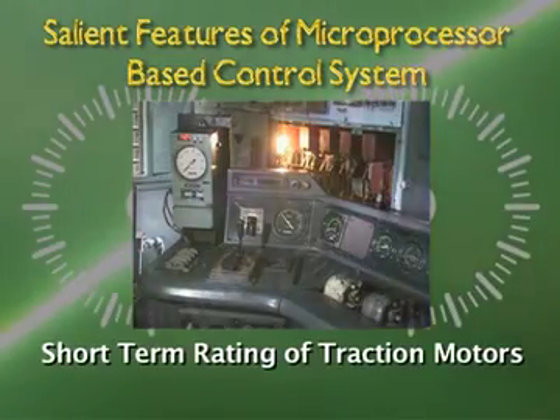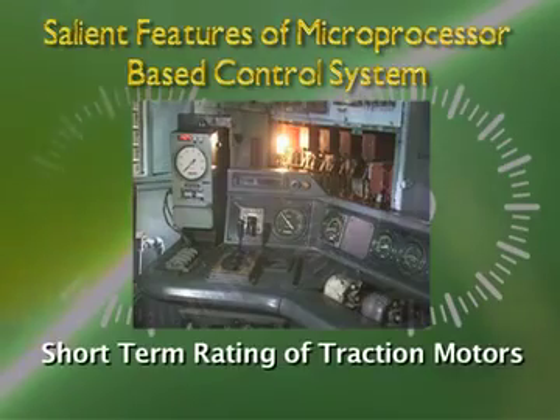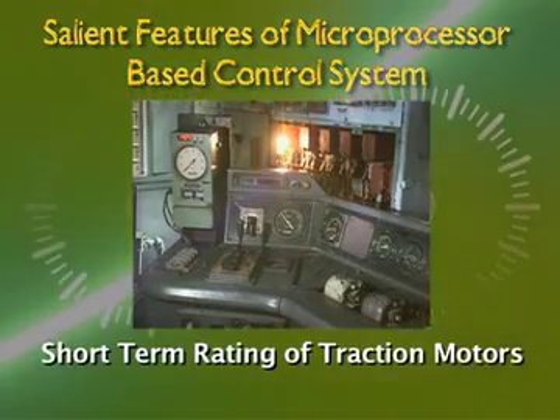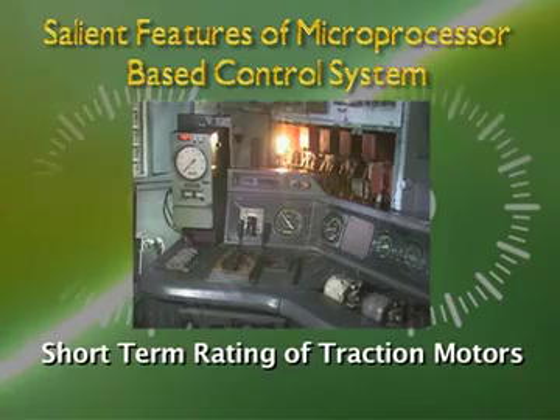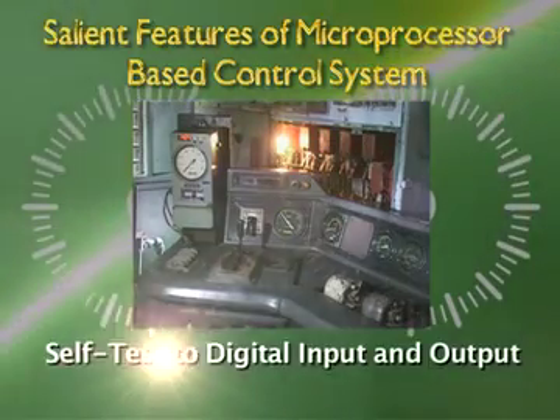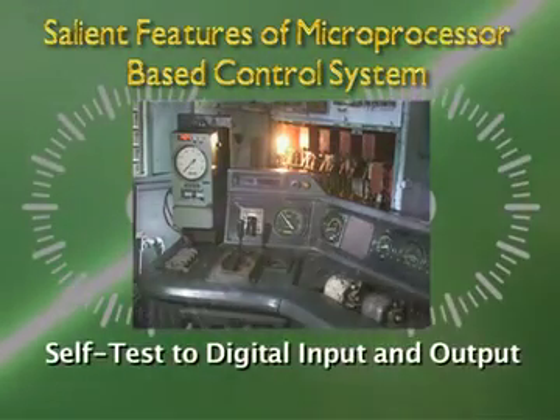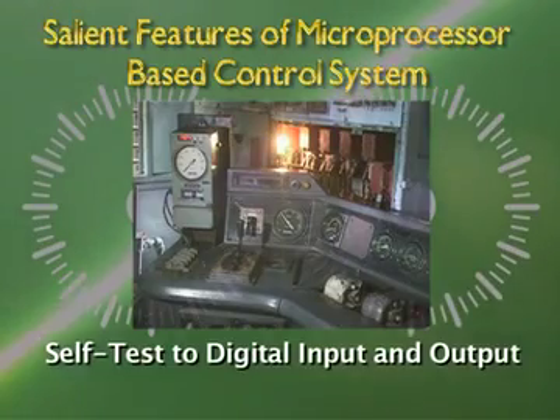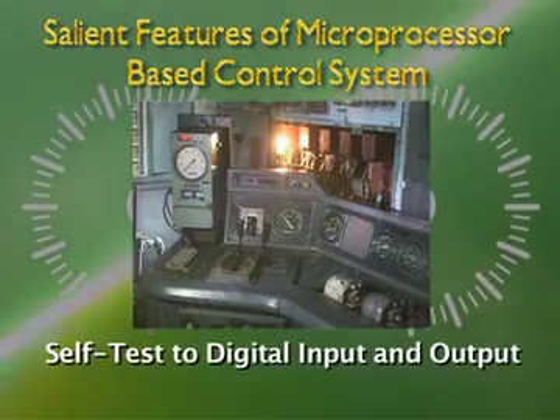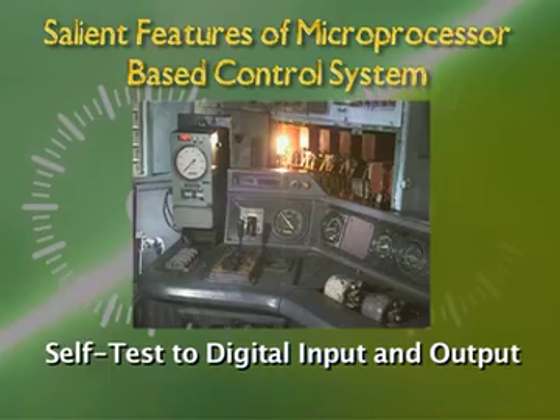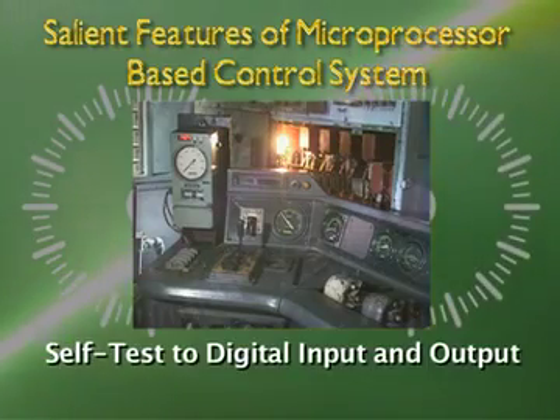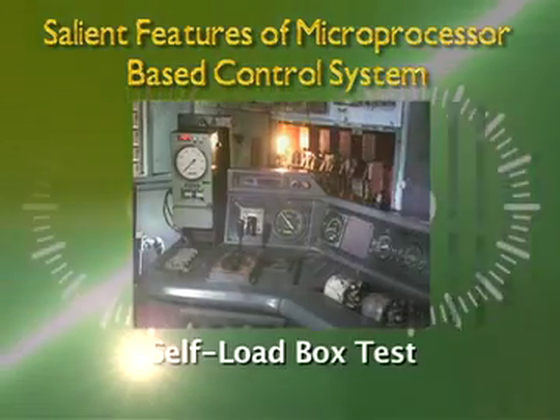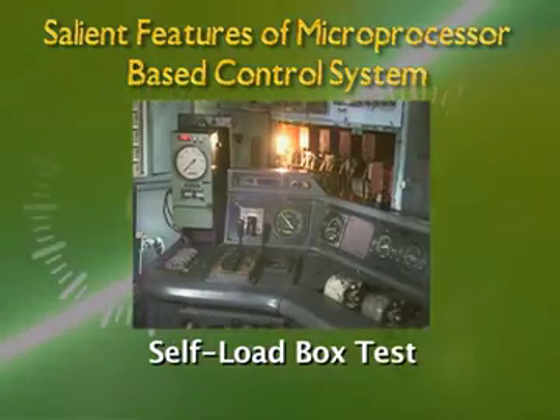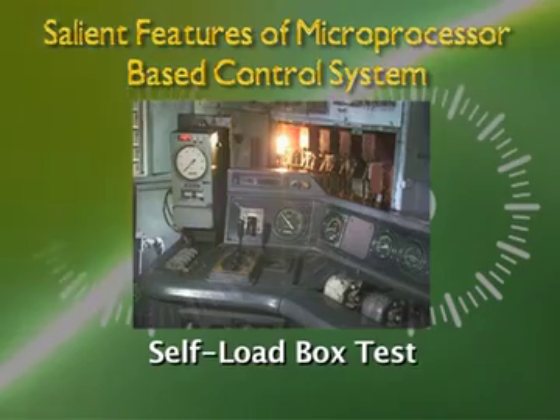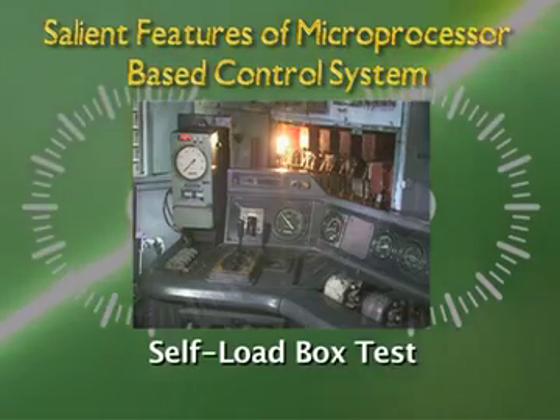Short-term rating of traction motors. The equipment automatically takes care of short-term traction motor current ratings and does not depend upon the driver for protection of the equipment. Self-test of digital inputs and outputs. MEP 660 has self-test facility for all digital inputs, outputs, and output devices, which enables the maintenance staff to identify wiring faults quickly. Self-load box test. A simple load test can be carried out to know the performance of the engine and entire control system.